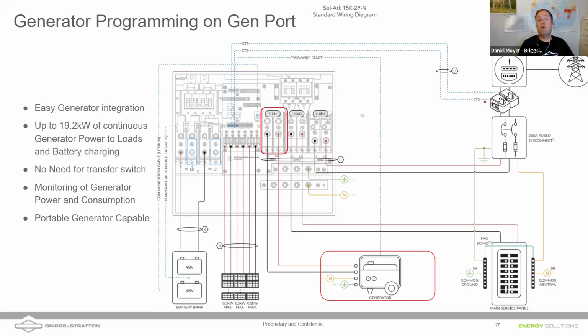Yeah, I think one of the nice things about a lot of these hybrid inverters, including the Sol-Ark, is that we don't want to overload the generator, right? We want to be able to program that generator so that the Sol-Ark does not exceed the capabilities of the generator. So aside from the sizing considerations and what loads we might expect, we do have the calculators available and we have sales application engineers to help you out. We want to make sure that we don't overload that generator. And Nathan, anything to add to that?